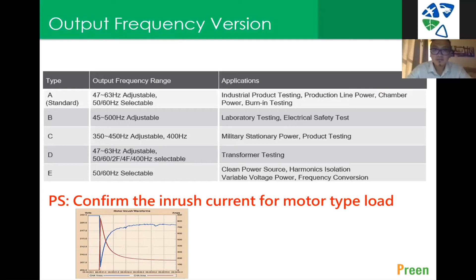So here is a comparison. If you are using a motor generator for changing the frequency versus using a variable transformer with AFC frequency converter, AFC is way more advantageous. That's why a lot of our customers, once they use AFC, they never turn on their motor generator again, because the motor generator is too noisy and has to be put outside the building, and sometimes it's diesel.